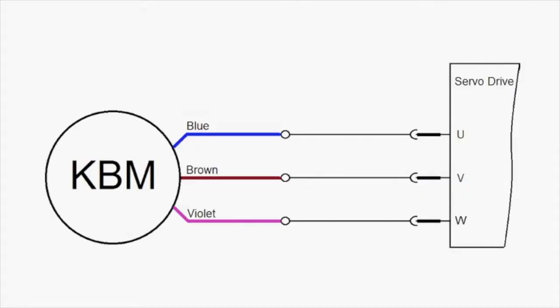If the motor has been mounted on the opposite side of the machine from what would be called standard, swap phases U and W. Check the phases on the scope.